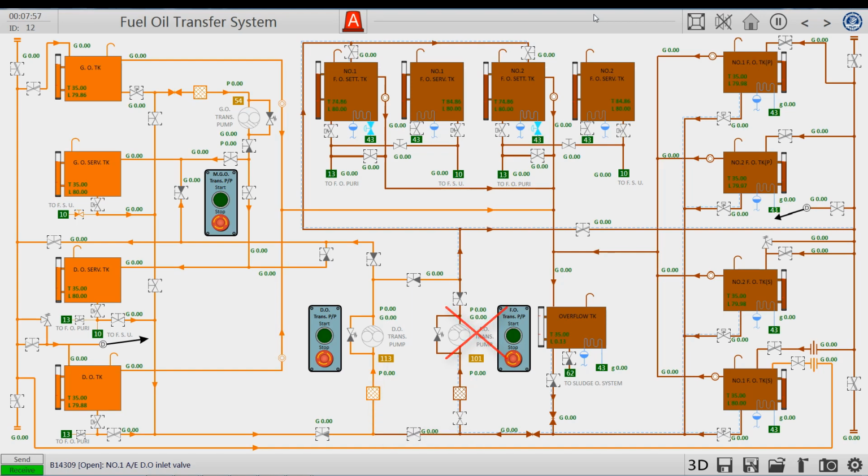We can see from the outlet of the light oil pump, where the light and heavy oil pipelines are related, a one-way valve is installed here. This shows that in the special case, we allow the use of the DO transfer pump to transport heavy oil. Namely, we see the DO transfer pump as a heavy oil transfer pump. However, the heavy oil transfer pump is not allowed to transport diesel. That is, the heavy oil transfer pump cannot be seen as a DO transfer pump.